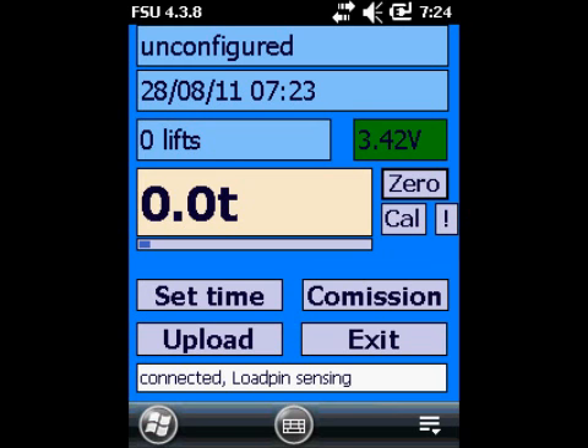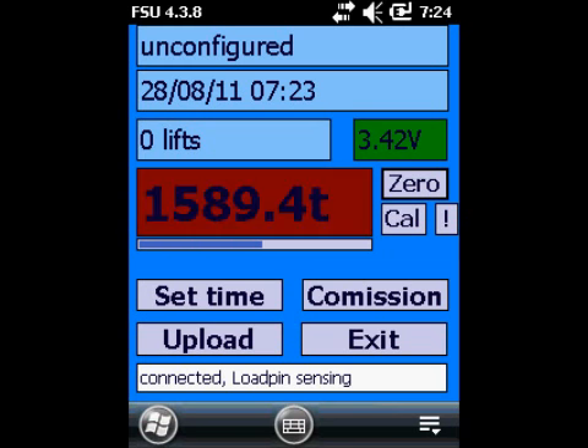Okay, the next thing we do is we lift a known load. We recommend at least 50% of the rated capacity of the crane. 80% is better, and this is true of most devices that want you to do a calibration. You need to lift a substantial load. Okay, so now I've got a load on the hook. I'm going to say this is a 10-ton crane. I'll tap on the cal button, and you can see that the bar has moved across to the right.